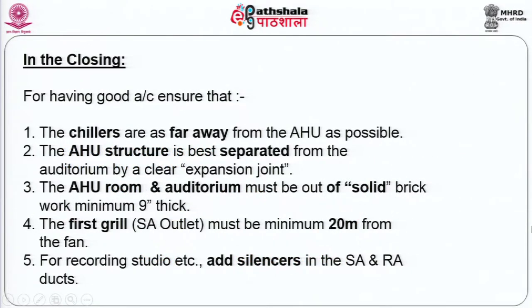Let me summarize what I have mentioned up to now. The chillers are to be kept far away from the air handling unit. The air handling unit should be separated from the air conditioned space by preferably an expansion joint, or at least a very heavy wall between the two. The first grill from the air handling unit should be a minimum of 20 meters from the fan. That means 60 to 70 feet away from the fan, so that the fan noise gets attenuated by the lining inside the duct. And if this does not meet the requirement, if by chance you have been stuck with equipment which does not perform, you need to add silencers.